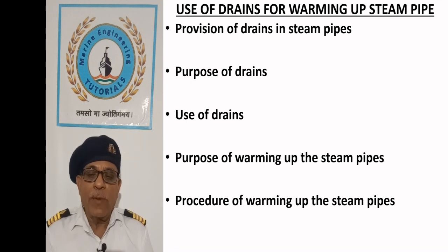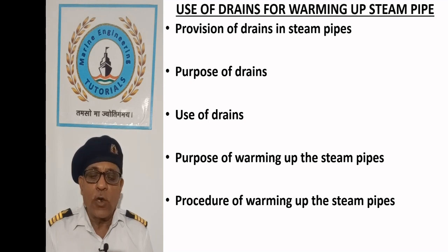For the purpose of warming up a steam pipe, a small sized warming up valve is usually provided, which acts as a bypass for the main valve. Use of a warming up valve prevents the damage to the valve disc and the seat of the main valve, which can occur due to throttling of steam, which becomes wire drawn and erodes the metal.